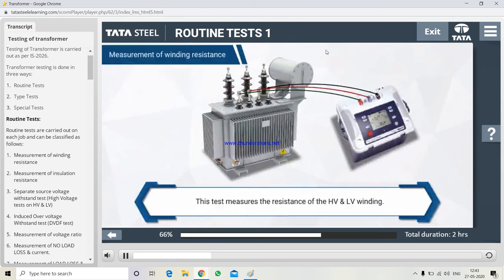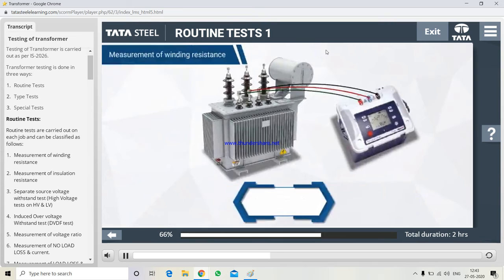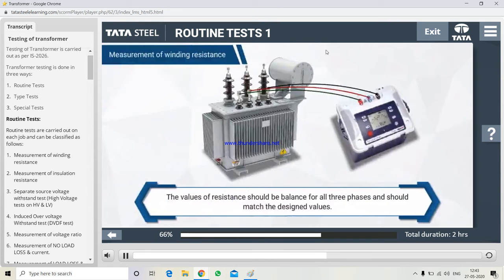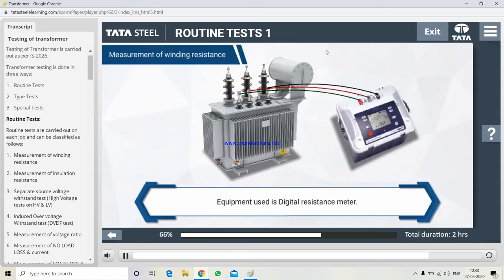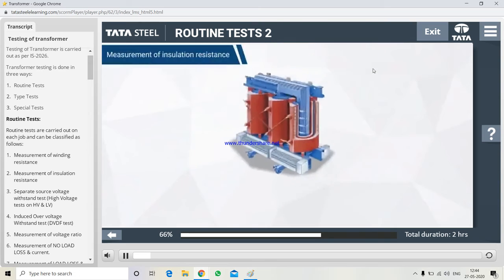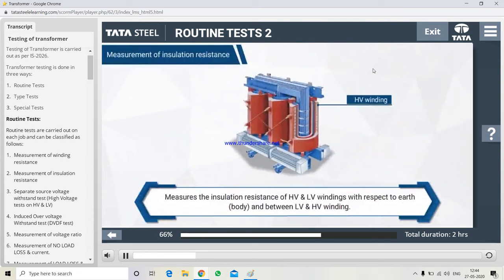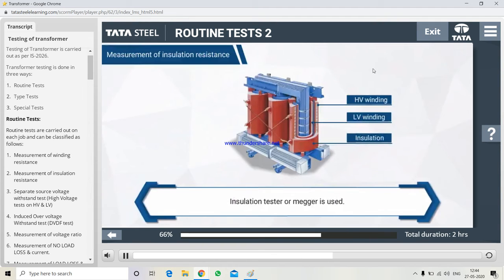This test measures the resistance of the HV and LV winding. The values of resistance should be balanced for all 3 phases and should match the designed values. Equipment used is digital resistance meter. Measures the insulation resistance of HV and LV windings with respect to earth, body and between LV and HV winding. Insulation tester or megger is used. Recommended values are 2000 megaohms for HV and 500 megaohms for LV.